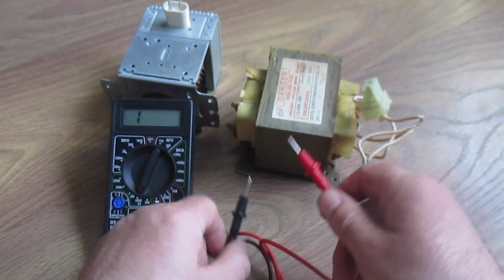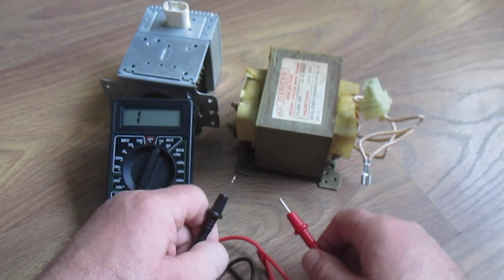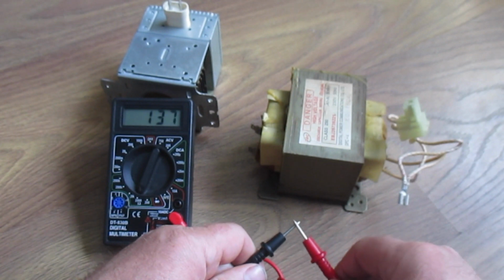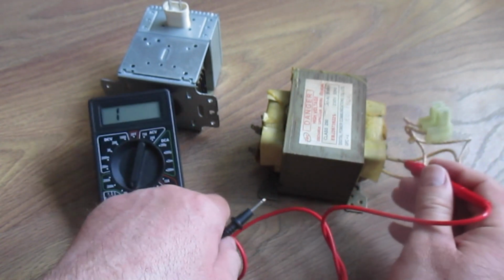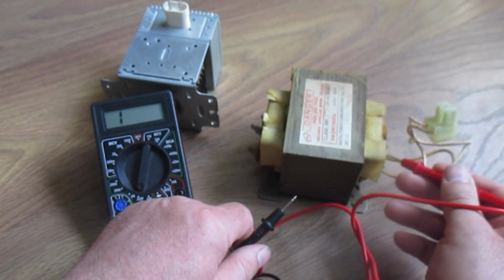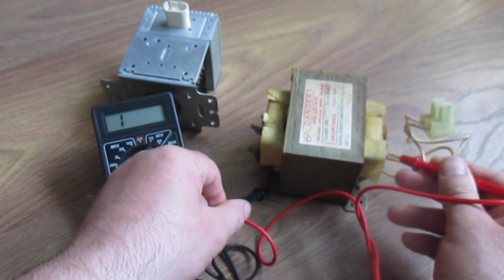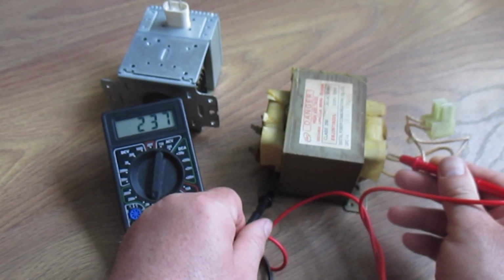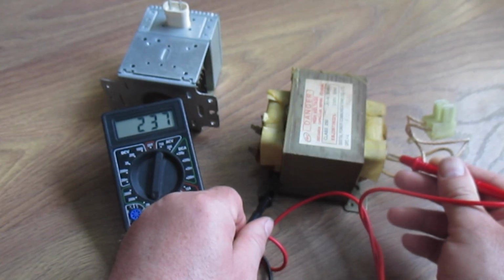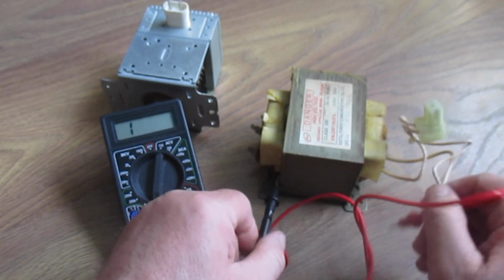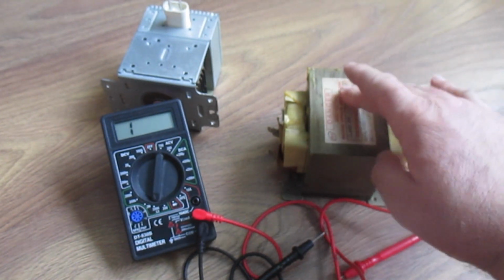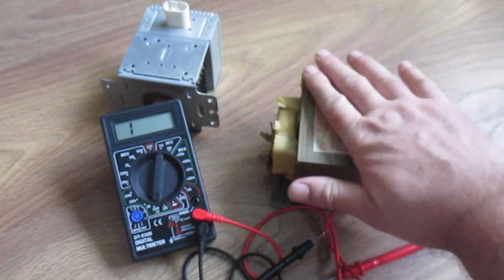Next, we check the secondary winding. To do this, set the multimeter switch to 2000 ohms resistance. Place the first probe on this contact and use the second probe to find ground on the case. The resistance shows 237 ohms, which is normal. The resistance limit here is 100 to 250 ohms. The resistance should be stable, without fluctuations. Also, if you notice that the transformer is humming and smoking, it is also unusable.